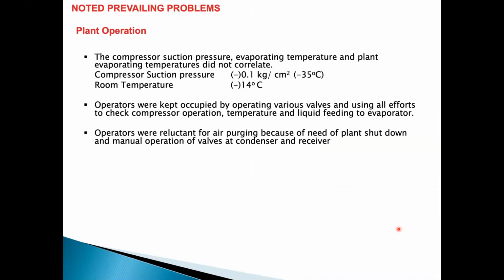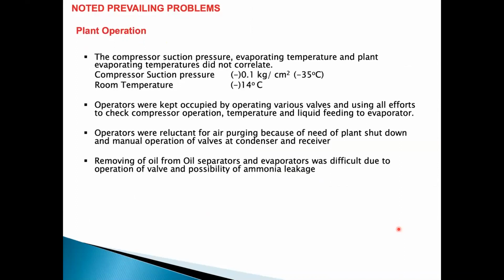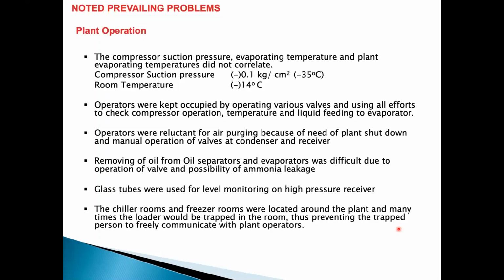The operator had to keep running around to operate these valves and run the whole system manually. Air was not being purged, because they had to shut down the plant and go to the condenser and receiver, and the operators did not find it convenient. Oil removal was very difficult because when draining oil there was always a possibility of ammonia leakage, and the valves were not able to close properly. For level gauges, the liquid level was not properly maintained because glass tubes were used, which normally broke and were never replaced.